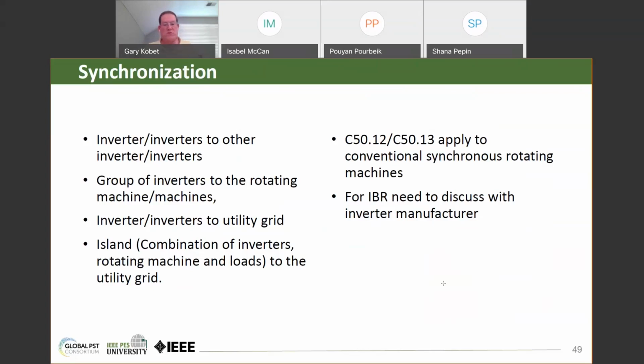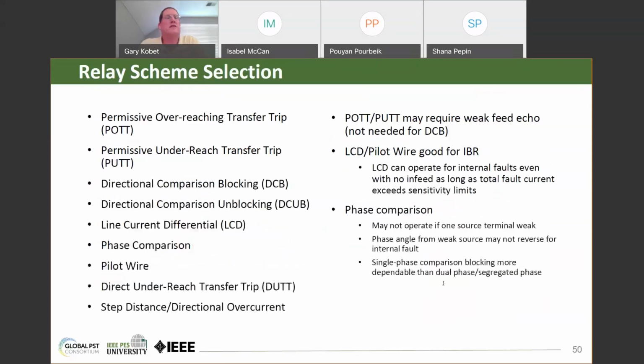And the next part of the paper talks about, on the next slide, relay scheme selection, and these schemes are well known throughout the industry, and the details of the schemes can be found in C37.113. But the paper addresses, and then some further work by the Power System Relay Committee discusses, some changes that may need to be made to different relay schemes. For example, permissive schemes may require weak feed echo. Blocking schemes won't require that.